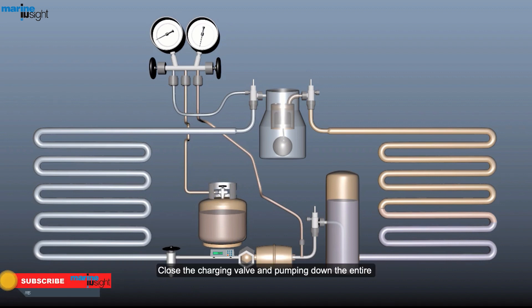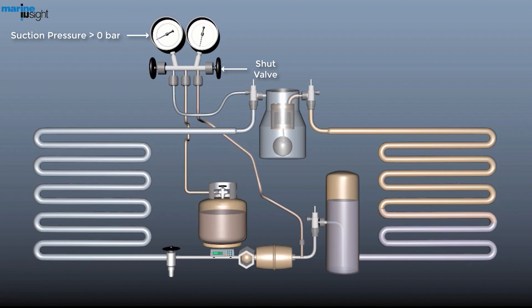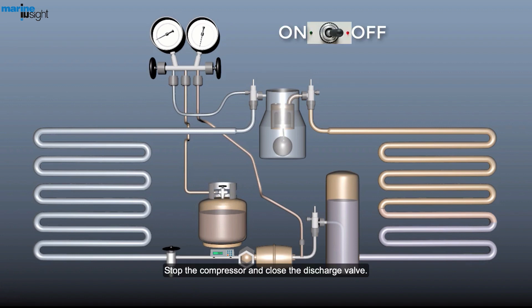Close the charging valve and pump down the entire charge until suction pressure is just above zero. Stop the compressor and close the discharge valve. Cooling water is kept running for some hours. Then air is purged out through the purging valve on the condenser until refrigerant gas appears at the valve.